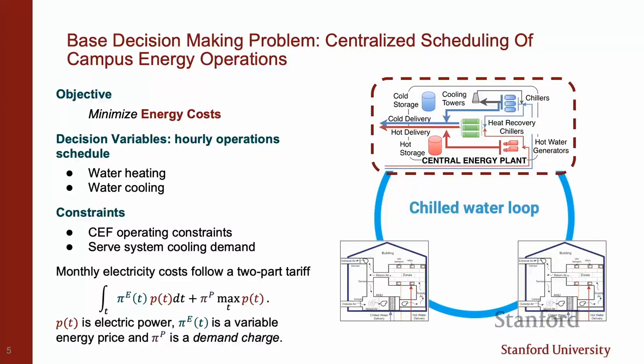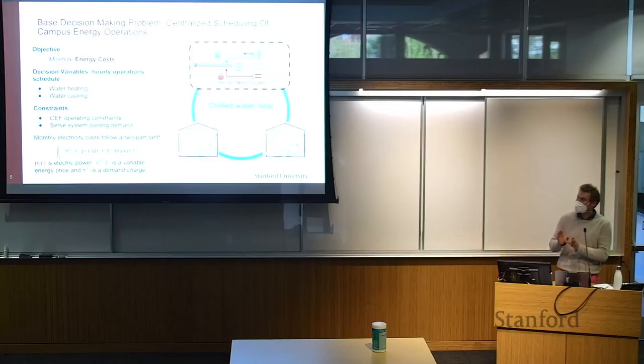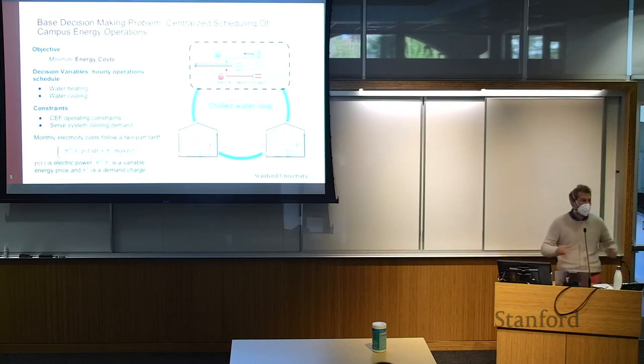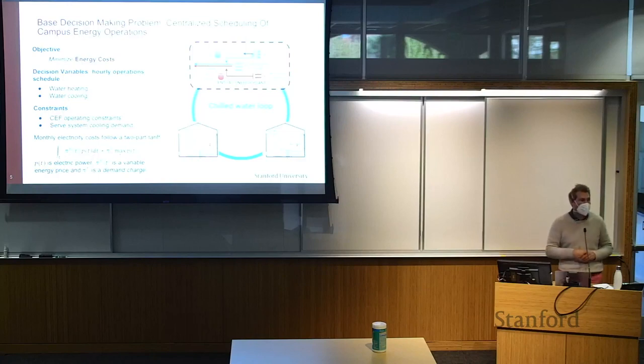We also pay what's called a demand charge — essentially looking at your maximum power draw over the course of the month and paying a price for that. An analogy: you pay both for volume and rate — the size of the pipe and how much went through it over the course of the month. Your main decision variables are how much to heat and cool water with each machine, with the option to store water, and the constraint that you need to give people their heating and cooling.